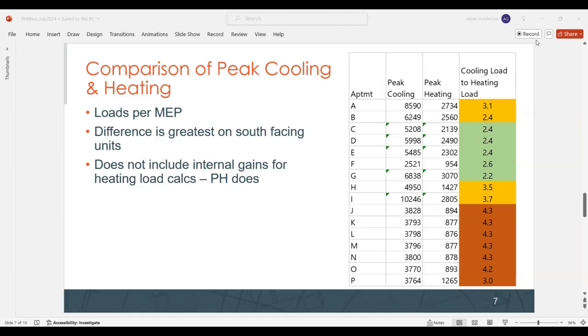I'd like to point out something as well, and that is that when we're sizing equipment based on the cooling load for a building as opposed to based on the heating load, we can take advantage of a lot more load diversity, right? And what that means is in the heating season, the entire building is pretty much at the peak heating condition at the same time, when it's the coldest hour of the coldest night. But in the cooling season, those cooling loads peak at different times based on the exposure, whether it's a southern exposure apartment or a northern exposure apartment, or whether someone's cooking dinner or not. So when you look at the building as a whole, those cooling loads per apartment are pretty low, but the cooling load for the building is even lower because there's a lot of diversity that we can take advantage of.